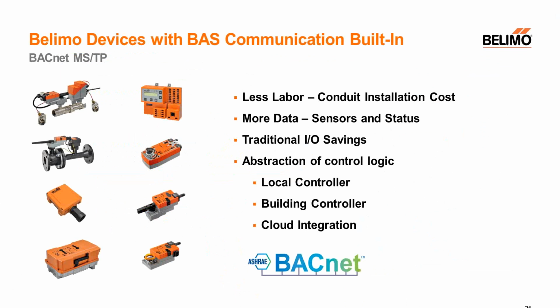You can communicate with them and control them. And then, looking to the future, it opens some doors to how we change what a control system looks like. You don't necessarily have to have the logic for whatever application this actuator is handling in the controller that it's attached to. The logic could remain there, or maybe the logic could be in a building controller that talks over BACnet to these devices, and then it opens the door for cloud integration.